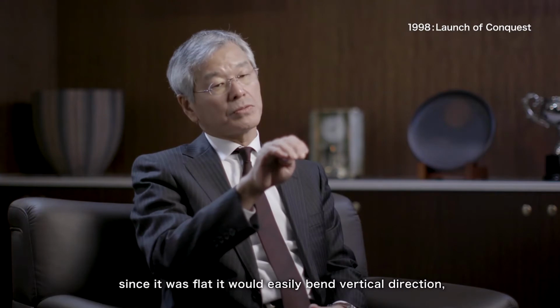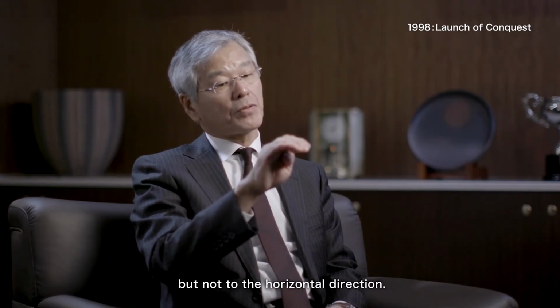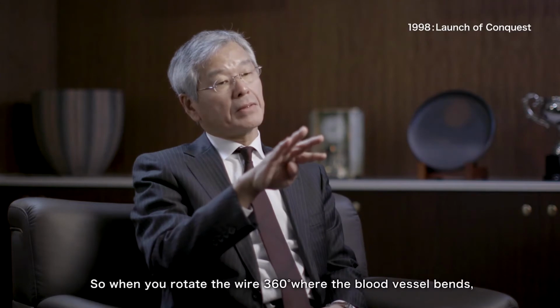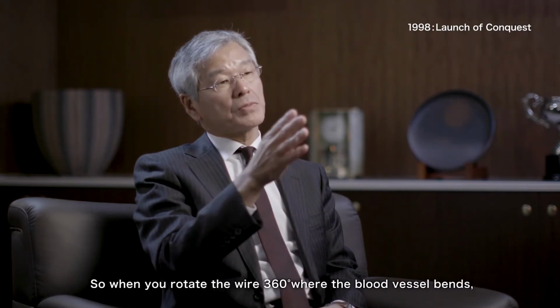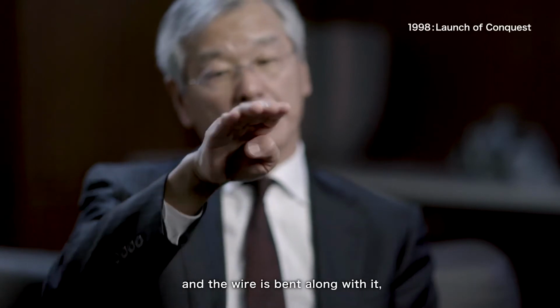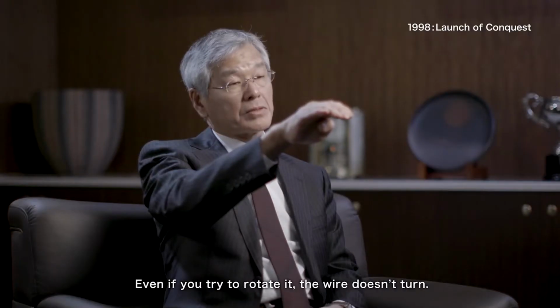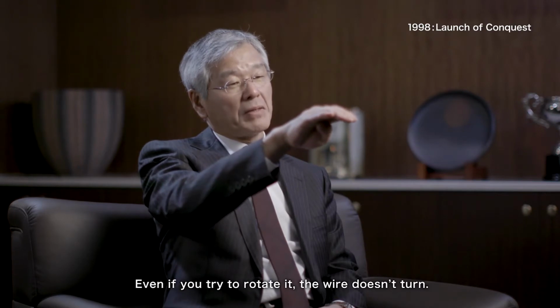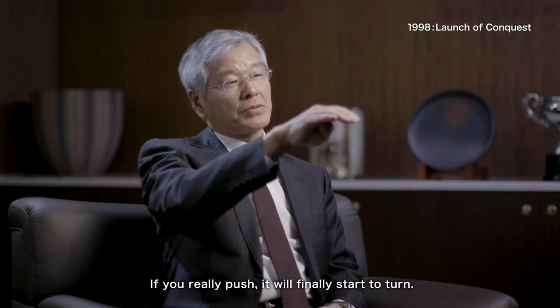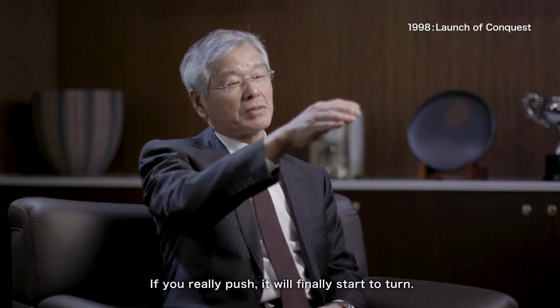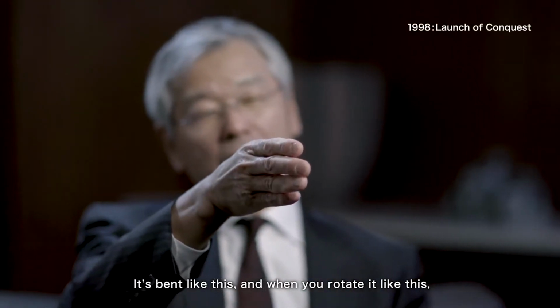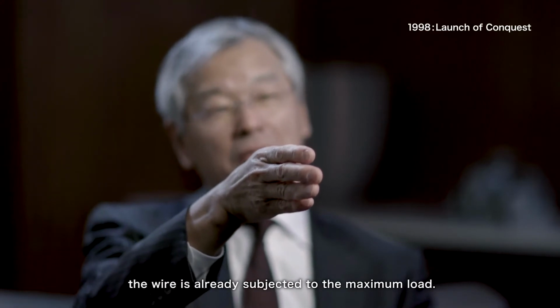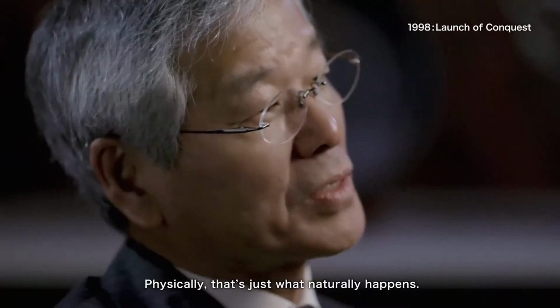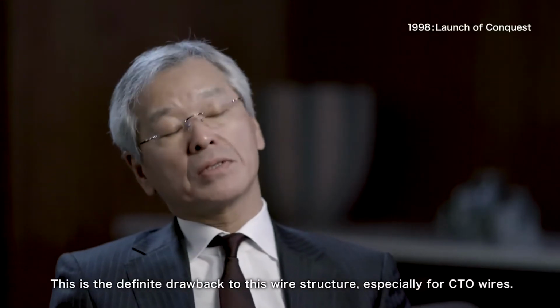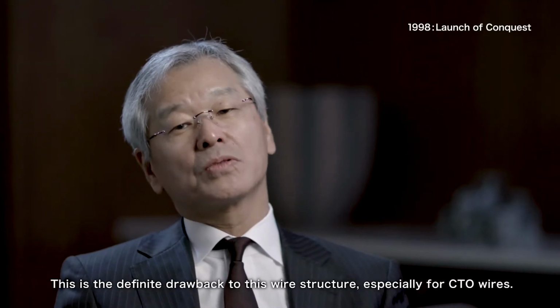Since it was flat, it would easily bend in the vertical direction but not in the horizontal direction. So when you rotate the wire 360 degrees where the blood vessel bends, the wire bends along with it, and even if you try to rotate it, the wire doesn't turn. If you really push, it will finally start to turn. It's bent like this, and when you rotate it like this, the wire is already subjected to the maximum load. You add just a little more and the wire suddenly whips. Physically, that's just what naturally happens. This is the definite drawback to this wire structure, especially for CTO wires.